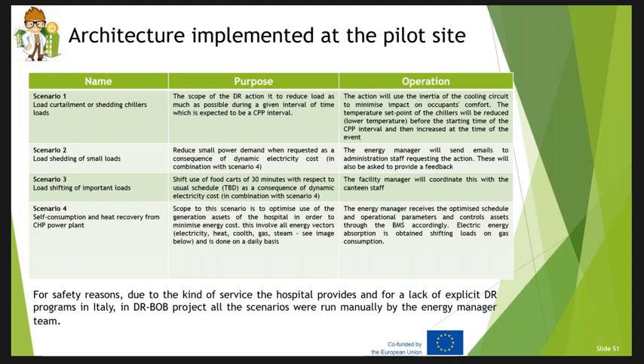In this scenario, to have a longer energy reduction in terms of time, we also pre-cool the water by 1 or 2 degrees Celsius before the event. The second scenario is shedding of small loads. We ask all the employees of the hospital to lower energy consumption by turning off PCs, monitors, printers, or lights, or anything easy for them to reach, for the period of the event.